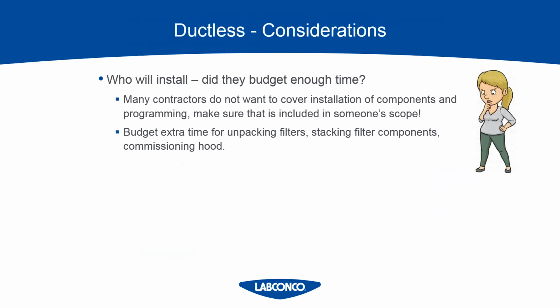So here, we have more considerations. Who is going to install the hood? If you have a ductless hood, make sure your installer scope includes more than just placing the hood on the work surface. Tell them that they will have to install the components above the hood, which includes stacking the filters and light and fan boxes on the DH3. It includes unpacking everything that needs to be stacked and also commissioning after it's installed. And then you'll need to budget extra time for all of that, and for troubleshooting if there are issues.